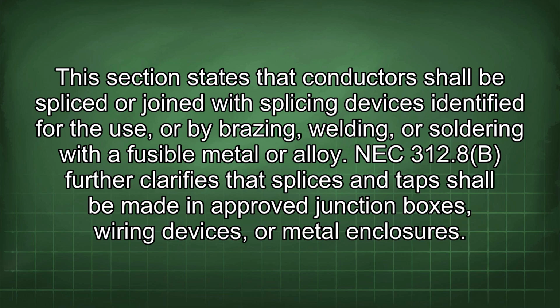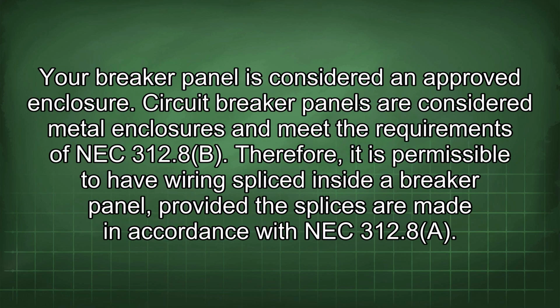NEC 312.8b further clarifies that splices and taps shall be made in approved junction boxes, wiring devices, or metal enclosures. Your breaker panel is considered an approved enclosure. Circuit breaker panels are considered metal enclosures and meet the requirements of NEC 312.8b.